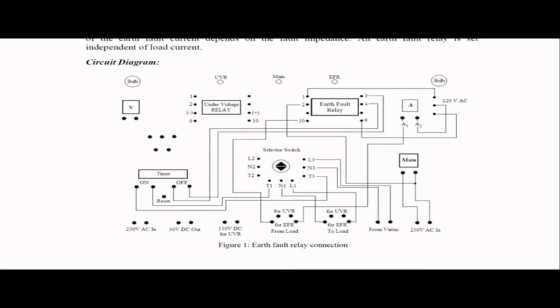Now what is called the relay operating time? Relay operating time means the time elapsed between the relay sensing the fault and the relay generating the trip signal. So the time required between these two events is called the relay operating time. The relay senses the fault, and after sensing the fault it generates the trip signal. That is the function of the relay. This trip signal goes to the circuit breaker, and the circuit breaker disconnects the faulty portions of the power system from the healthy system. So the function of the relay is to detect the fault and to initiate the trip signal which is required to operate the circuit breaker.